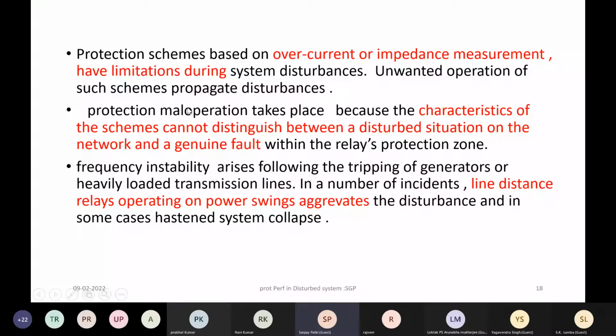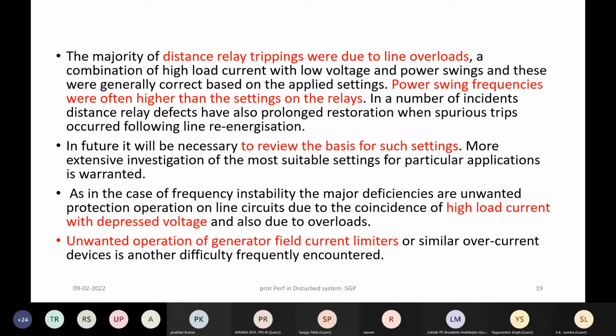So the main challenge is how the protection relay, because the protection relay will only see the impedance as it swings, determines whether the swing is due to a fault, because when a fault takes place, the impedance change is there at that time also. The rate of change of impedance will be different, though. During a power swing, the rate of change of impedance will be different, and so this can be one of the criteria by which the relay will distinguish between a power swing and a fault. So this is basically one of the major protection review points.